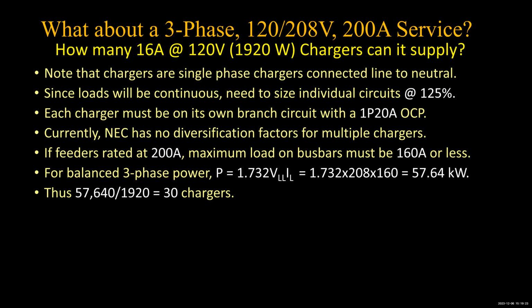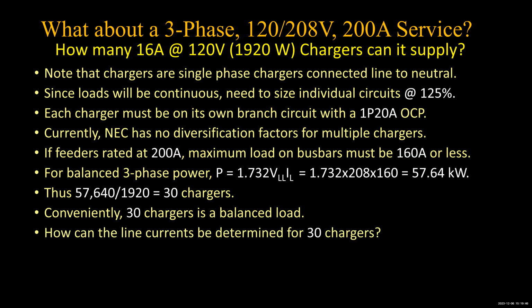And this is realistic in a place like a condominium, to use a single three-phase 200 amp service to service and charge up a whole lot of vehicles. And the nice thing about 30 is that's 10 chargers per phase, a nice balanced load. So you can't beat that. So how do you know what the line currents are for 30 chargers?